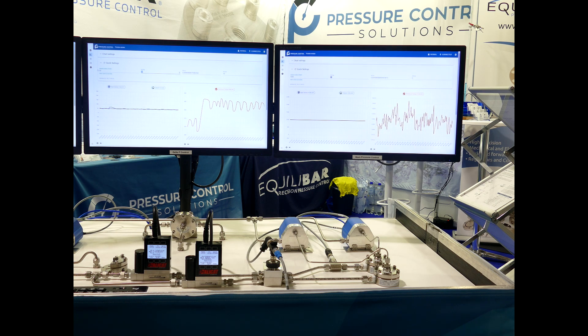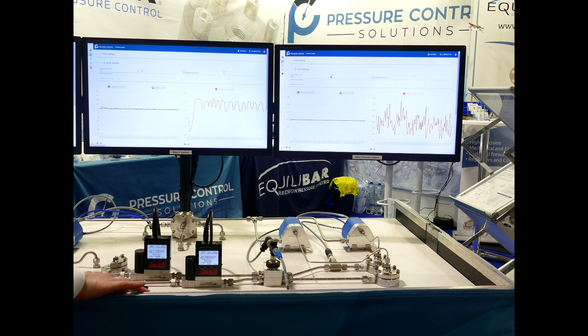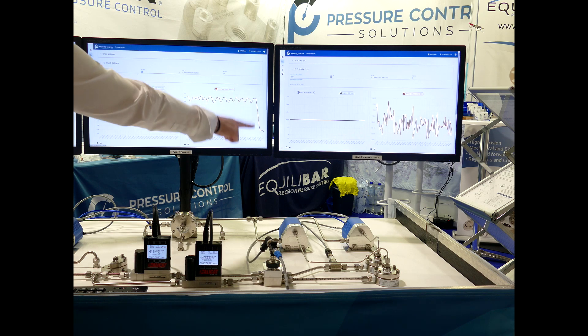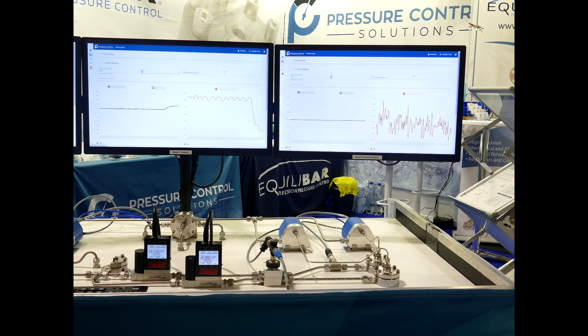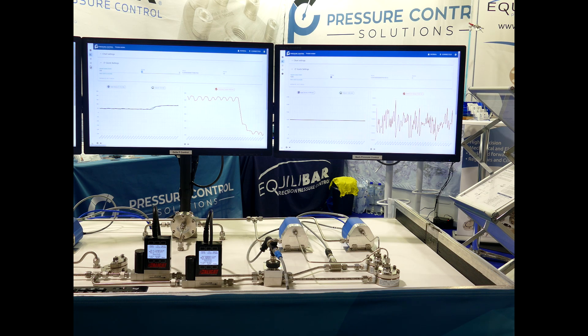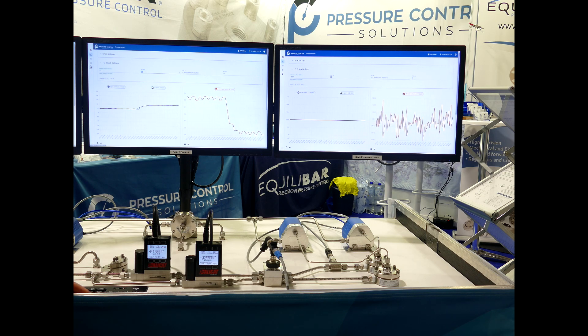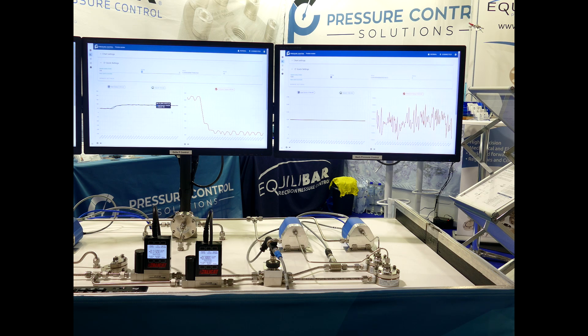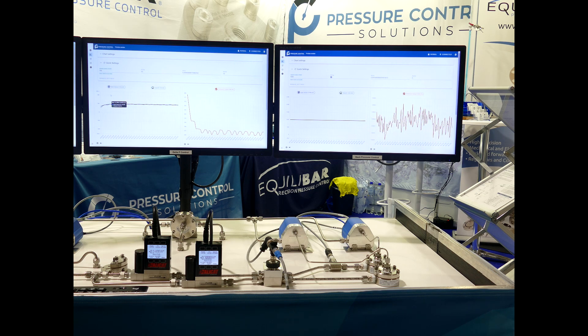I can also change the set point of the differential pressure to a higher value. Here you can see the reaction on the EQDA — it will lower the pressure on the diaphragm to match the process value with the new set point. As we have seen, the reaction is very fast and the new set point is reached.